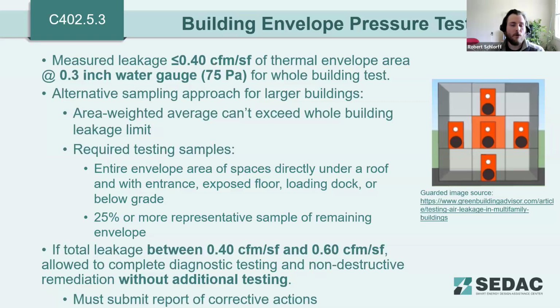So this is basically saying that, well, you're close, but you're not exactly there yet, but you're within this little buffer zone. So we won't make you test again, but you do need to go around the building with some diagnostic testing, potentially smoke pencils, thermal imaging, something like that. Perform any non-destructive remediation that you can, and then the code will say that you have complied with this requirement. So again, there's a little bit of a performance buffer there.